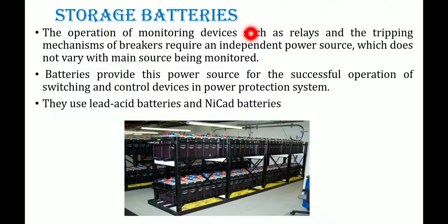So the reason, as I said, is the operation and monitoring of devices such as relays. The relay sends information regarding the fault that has taken place in the system, and by that information the breaker trips. The tripping mechanism requires an independent power source, provided by these storage batteries. The battery is nothing but a DC power source, providing power for the successful operation of switching and controlling devices in power system protection.